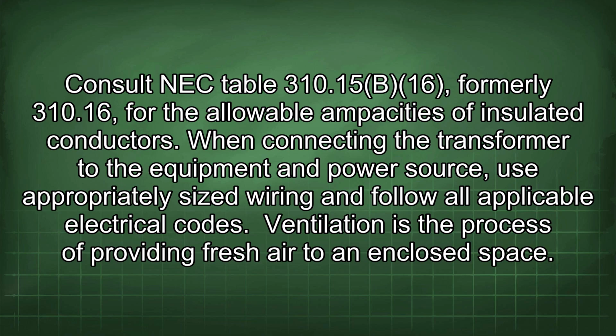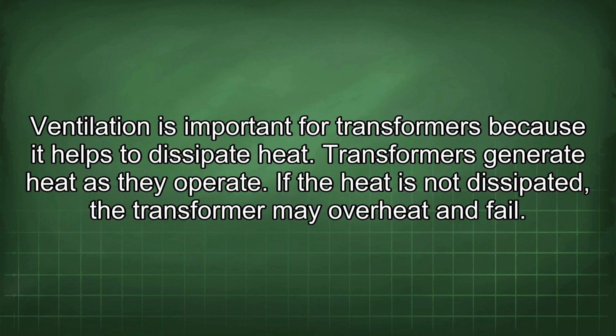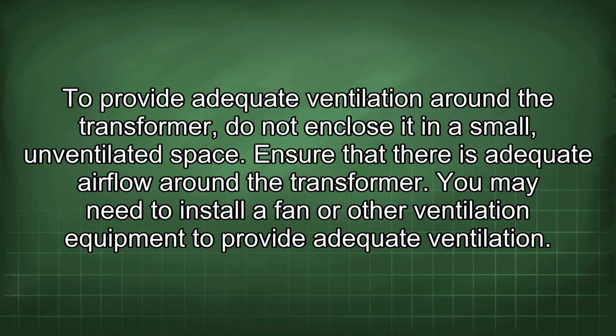Ventilation is the process of providing fresh air to an enclosed space. Ventilation is important for transformers because it helps to dissipate heat. Transformers generate heat as they operate. If the heat is not dissipated, the transformer may overheat and fail. To provide adequate ventilation around the transformer, do not enclose it in a small, unventilated space. Ensure that there is adequate airflow around the transformer. You may need to install a fan or other ventilation equipment to provide adequate ventilation.